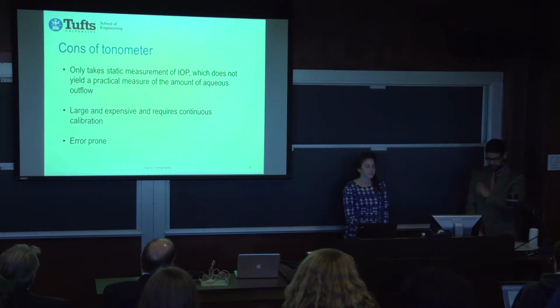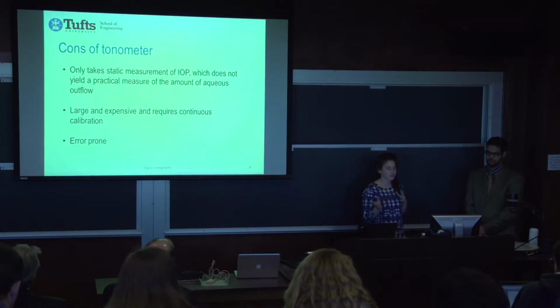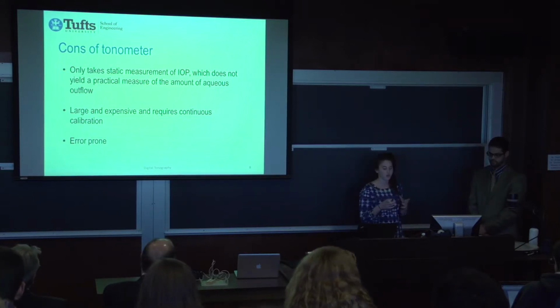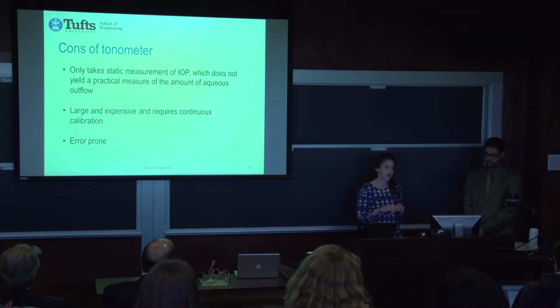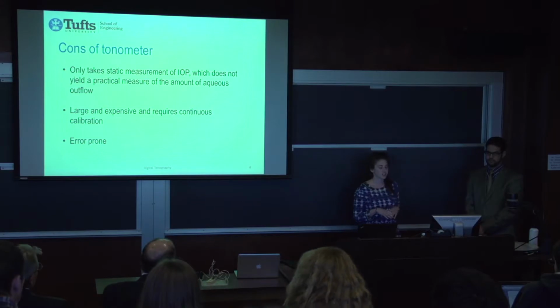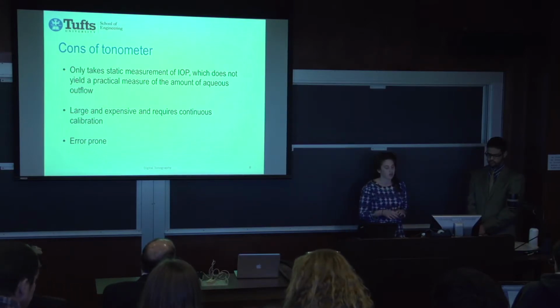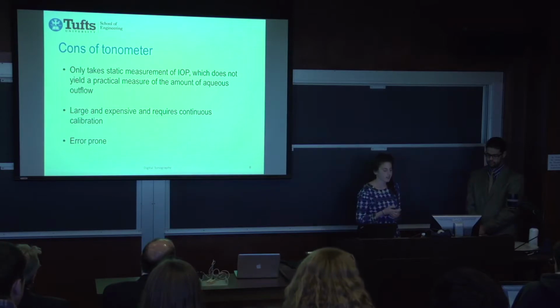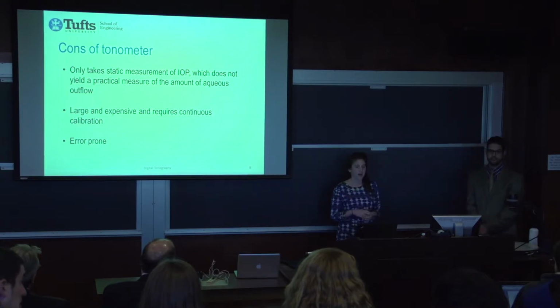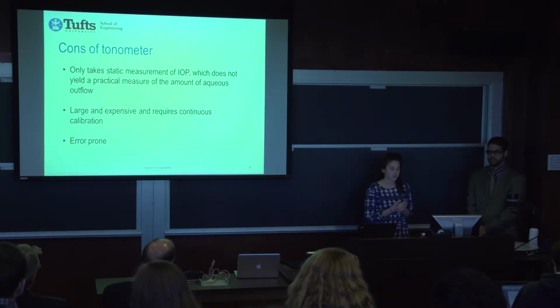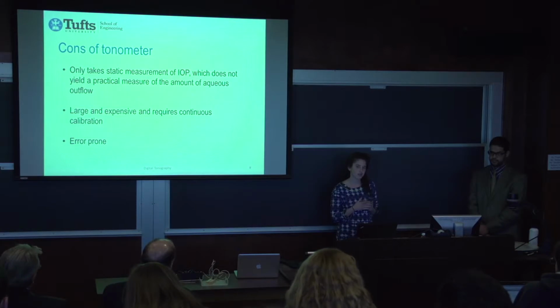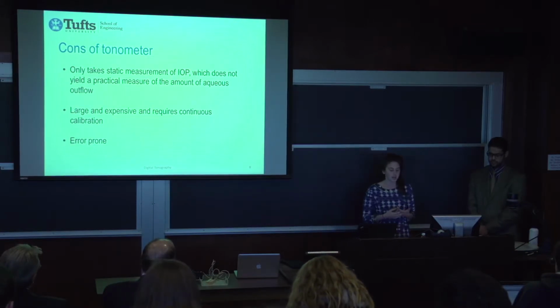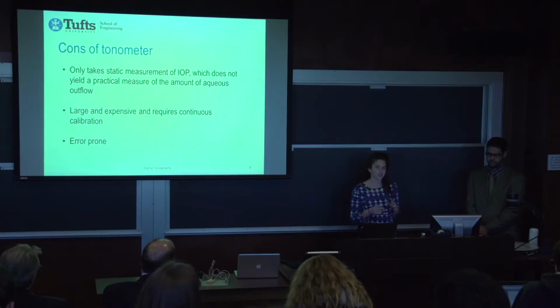Generally, applanation techniques like Goldmann's have totally replaced the indentation technique represented by the Schiotz instrument that I described earlier. This is primarily because the Goldmann reading can be taken with little disturbance to the eye, unlike the heavy weight and corneal indentation associated with the Schiotz tonometer, which actually causes a noticeable increase in the pressure of the eye during the assessment, unlike the Goldmann tonometer. But one aspect of this raised IOP during the Schiotz tonometry test still makes it more advantageous compared to even today's tonometers, which is that it is able to make an estimate of aqueous outflow by a test called tonography.